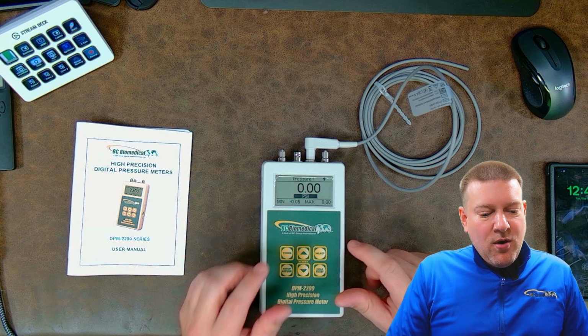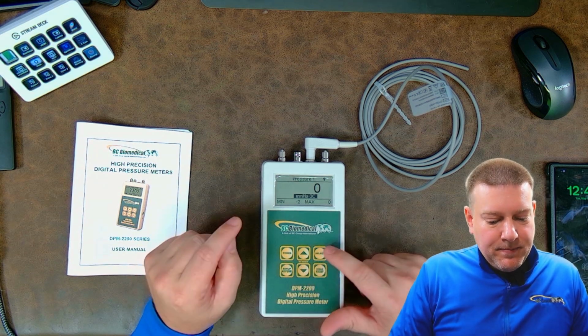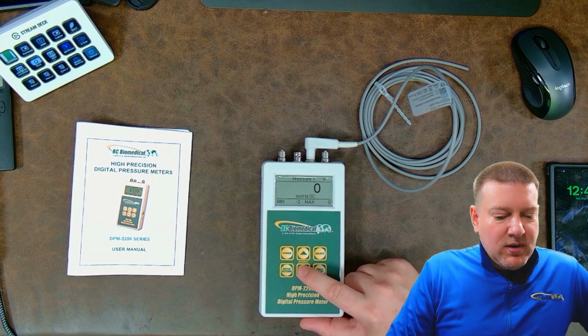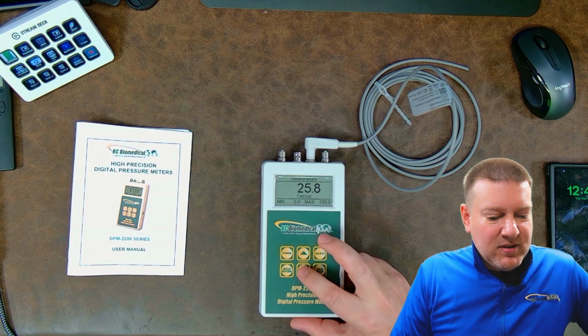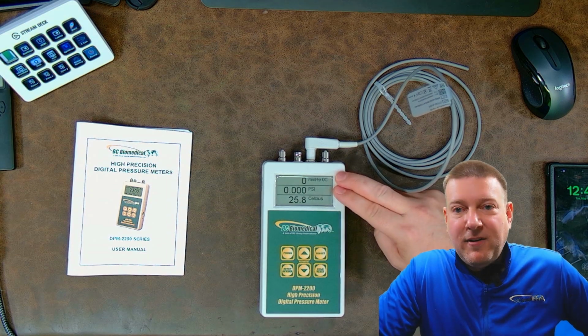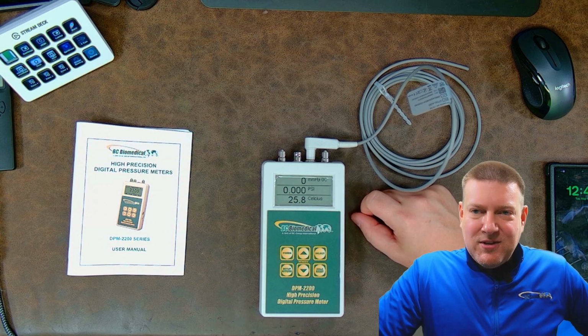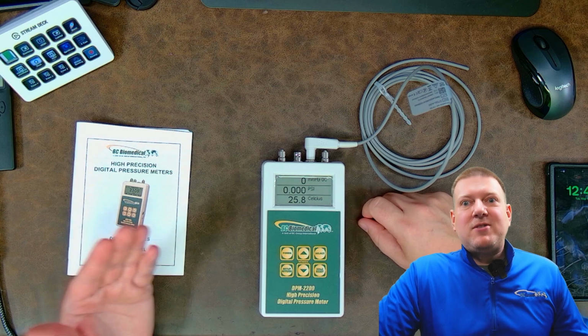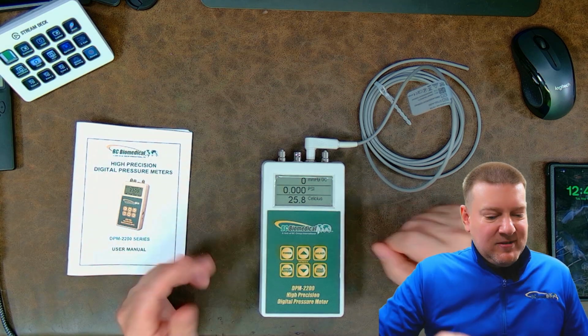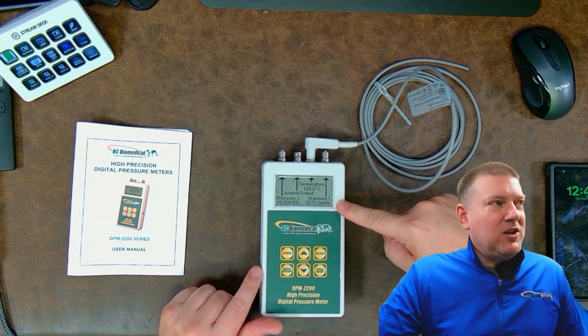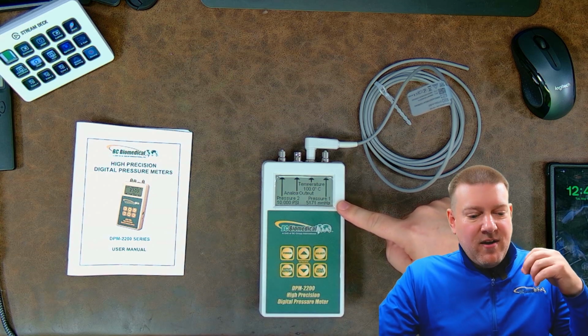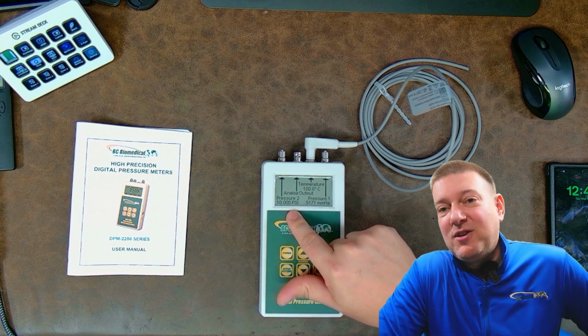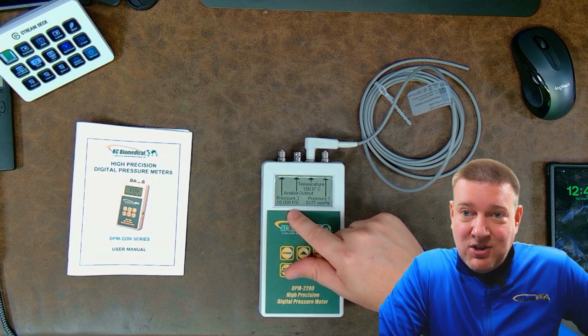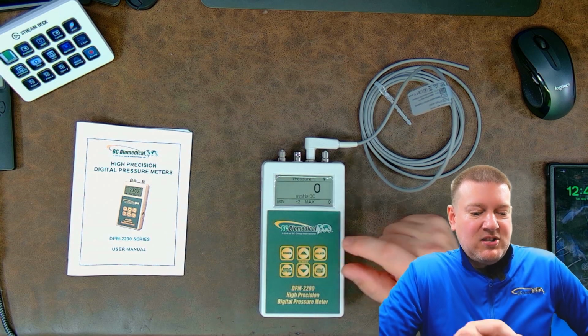Now the cool thing is you can set one pressure transducer to measure in one unit, and then set the other transducer to measure in a separate unit. When you go down to this screen here, you can have two different units reflecting on the exact same page, which is really unusual, because usually if you move your meter to millimeters of mercury, all the measurements are going to be in millimeters of mercury. Independent measurement units. Very cool. Temperature on the same screen, super nice. I also dig this right here. Notice that when I change my units, it changes the cap. So instead of just saying 100 psi, notice how pressure number 1 moved to 5,171 millimeters of mercury. Meanwhile, pressure 2 is still sitting at 10 psi, because I changed the engineering unit. Very cool that it's a live screen that changes like that.